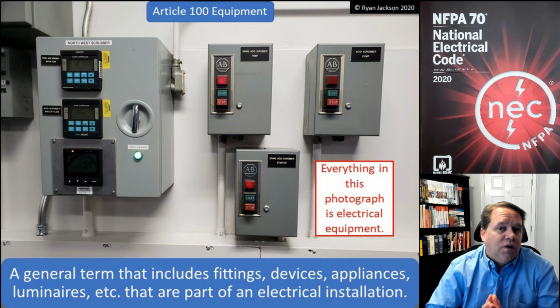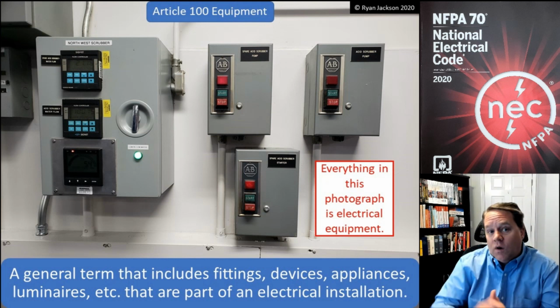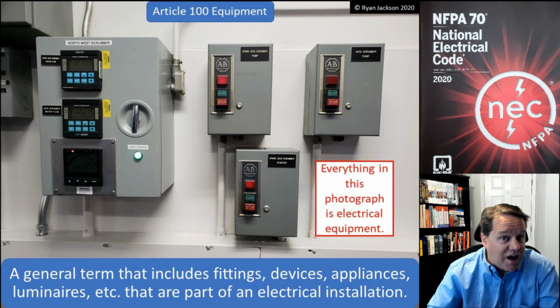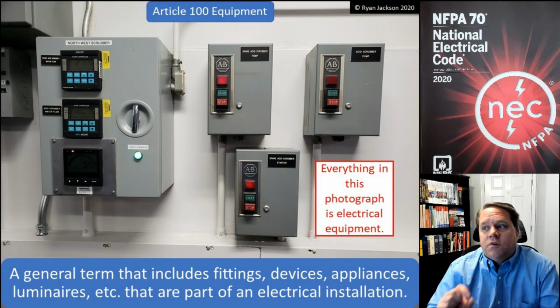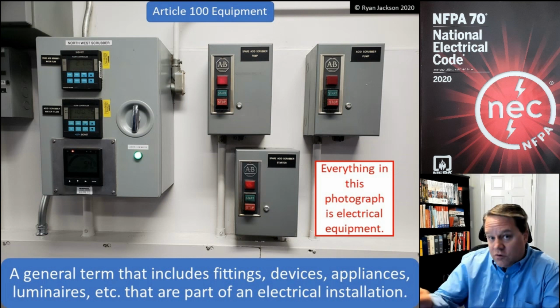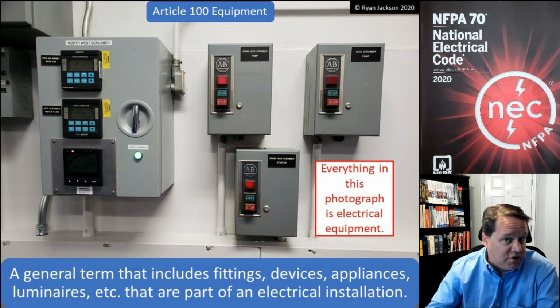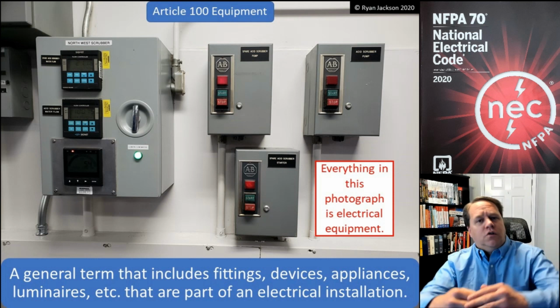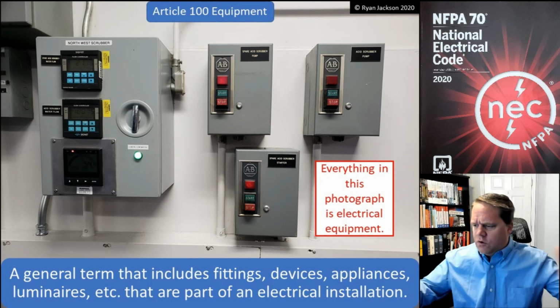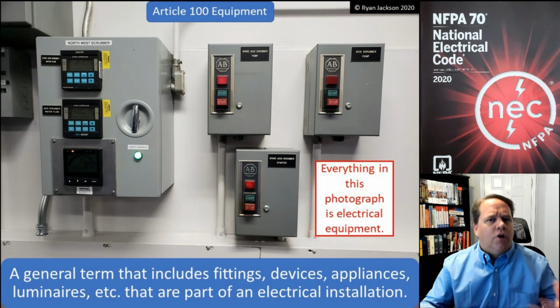That's what 110.26 says. Now, if you go deeper into 110.26(A), it talks about specific rules for equipment that's likely to require examination, adjustment, servicing, or maintenance while energized. And that's where you might get your 3 feet and your 4 feet and 30 inches wide and 6.5 feet tall and all that stuff.